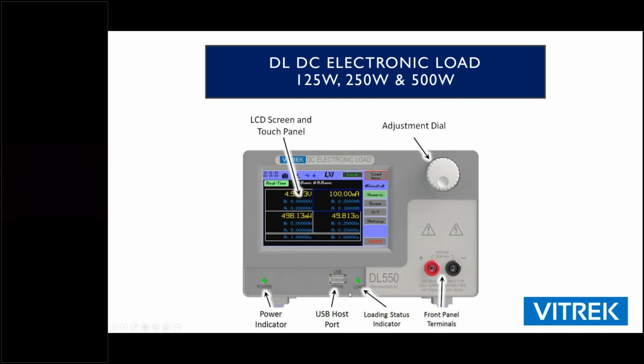You can see that we also have the USB drive on the front. That's where you're able to pull down your screenshots, or store some test results. Loading indicator, you're going to see in 2 spots: we've got a green light on the front, and also on the screen you'll see if the load is on or off. For your convenience, we also have front panel terminals, limited to 30 amps, which is going to be fine for most applications.